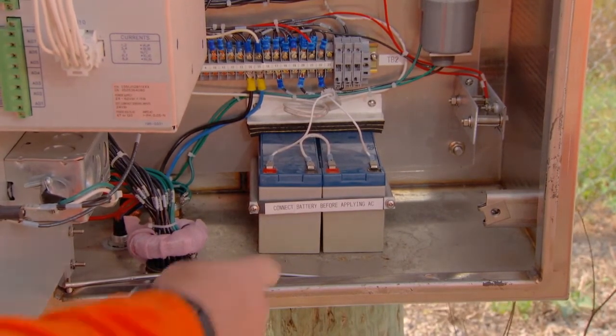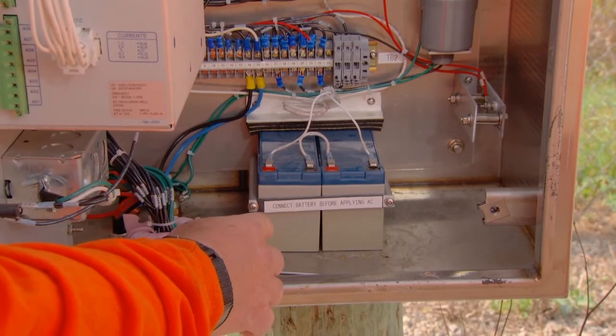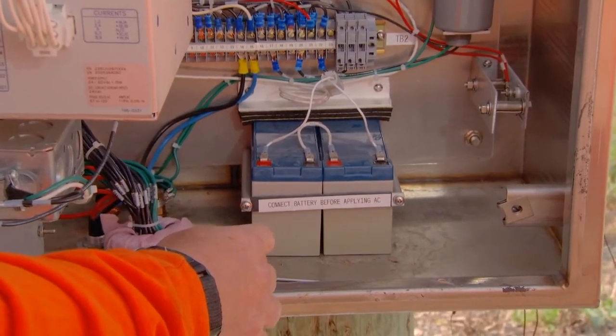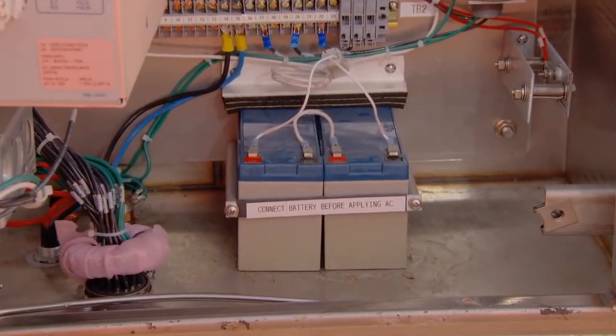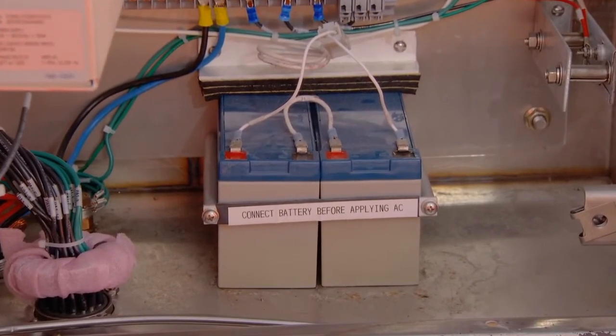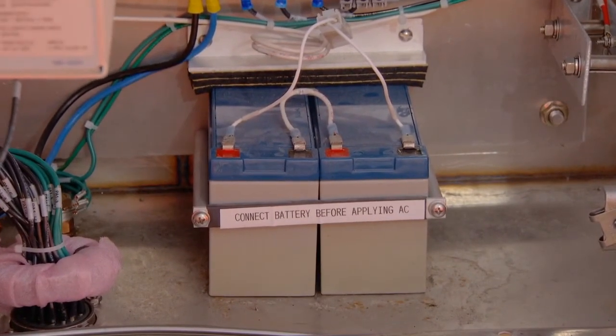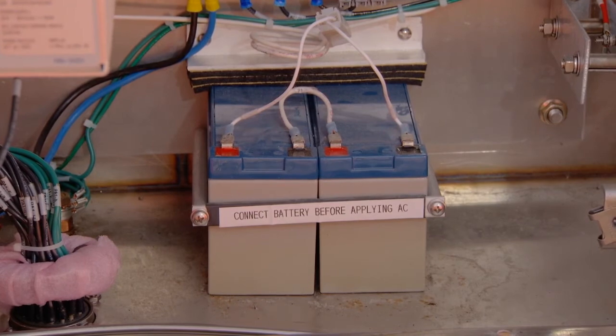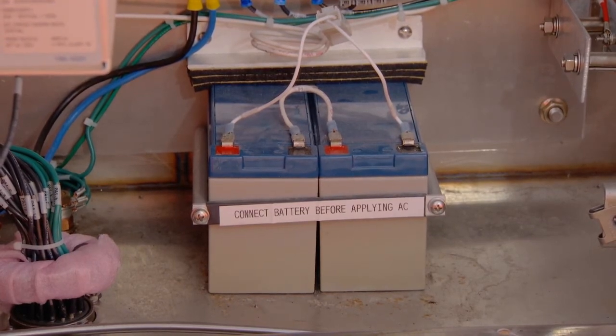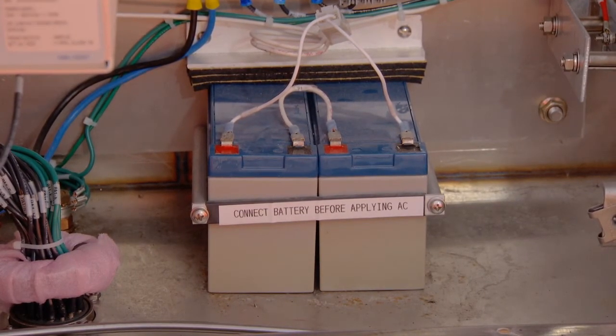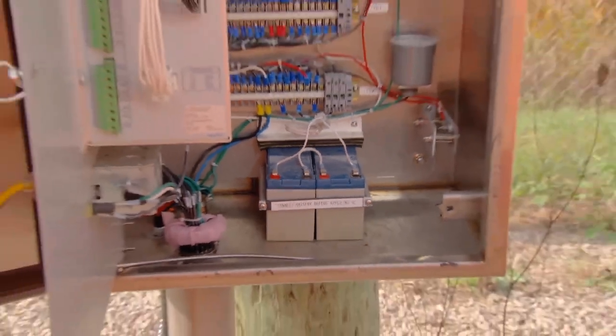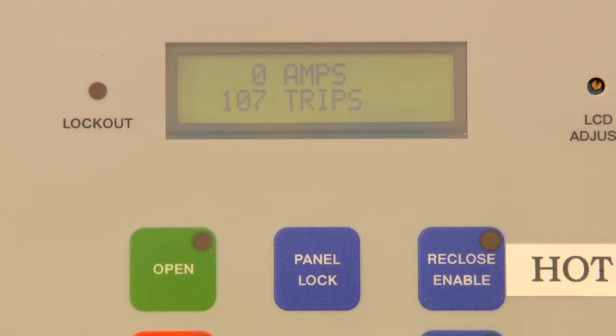At the bottom of the enclosure, we have the battery backup system. There are two 12-volt batteries in series providing a total of 24 volts. If the AC is lost to the controls, the batteries will hold the unit's functionality for up to 24 hours. As you can see from the warning notice, always connect the battery before turning on the AC supply to the control. Let's review the display features as we look at the default screen.